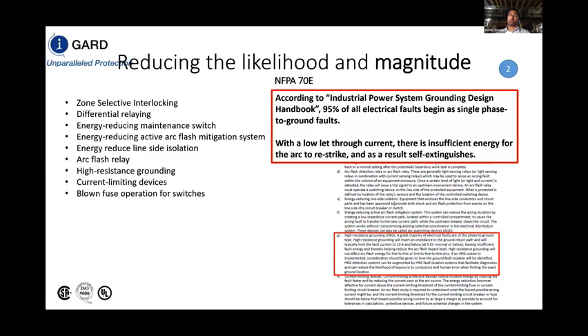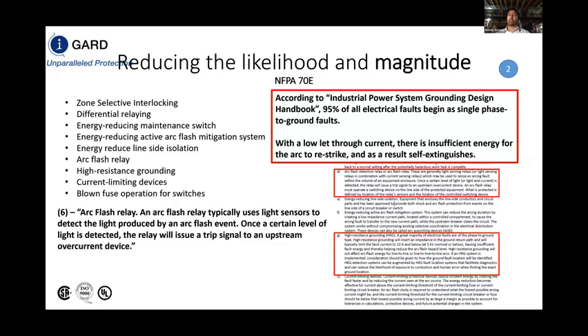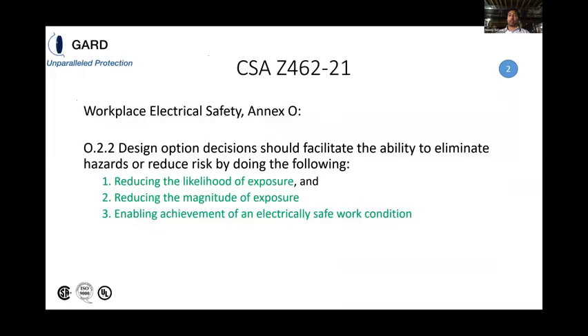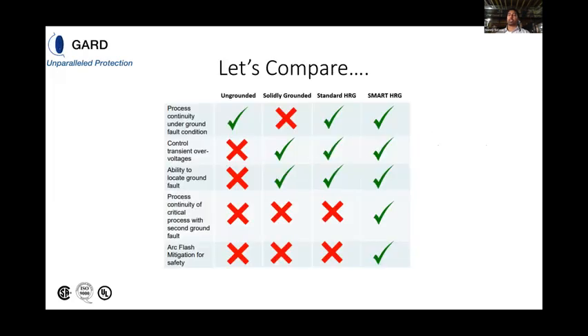So what we did at iGard is we implemented an arc flash detection relay alongside our resistance grounding solution so that we can handle the magnitude approach by capturing the particular spectrum of light emitted by an arc flash incident and tripping the upstream breaker within 1 millisecond is when we're sending the signal out. Now, with the combination of this arc flash relay and the high resistance grounding system, we're essentially meeting Annex O.2.2 and reducing the likelihood of exposure, reducing the magnitude of exposure, and enabling achievement of an electrically safe work condition. So now you can see that Smart HRG is advancing on just the standard HRG offering and providing these additional benefits of second ground fault protection, as well as arc flash mitigation for safety.